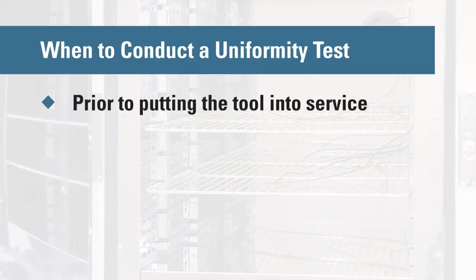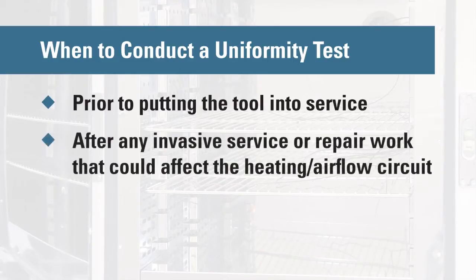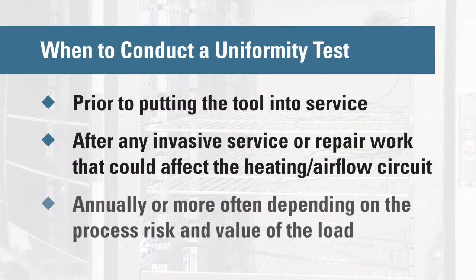After any invasive service or repair work that could affect the heating airflow circuit, and annually or more often depending on the process risk and value of the load.